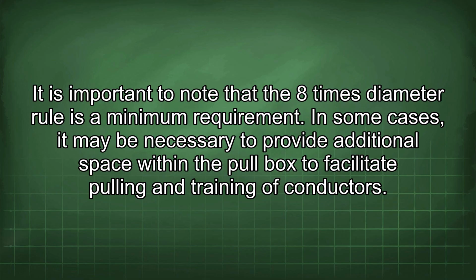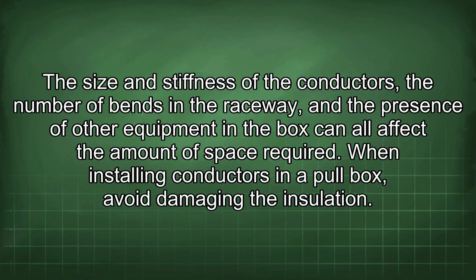In some cases, it may be necessary to provide additional space within the pull box to facilitate pulling and training of conductors. The size and stiffness of the conductors, the number of bends in the raceway, and the presence of other equipment in the box can all affect the amount of space required.